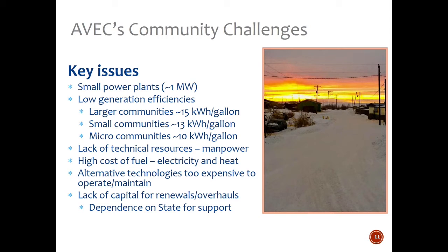What I've seen from standalone communities not part of the AVEC system is that there are no resources to undertake a routine generator maintenance program. So all too often a brand new generator in service for 3 or 4 years fails because you haven't done your overhauls or changed the oil. Then suddenly you have a massive expense to replace that generator, and you limp along for years on this failure-replacement cycle. That's what needs to change, and that's what AVEC does - we break that cycle, but it's not cheap.